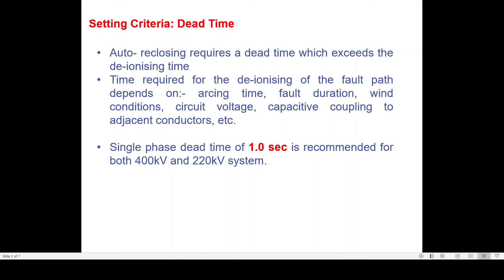Generally, dead time depends upon the arcing time of the circuit breaker, the speed of the circuit breaker — that means how quickly the moving contact separates from the fixed contact — the fault duration, wind condition, circuit voltage, as well as the capacitive coupling between adjacent conductors. For 220 kV and above, the dead time is selected as one second, but some utilities also select dead time as 600 or 800 milliseconds. This generally depends upon the circuit breaker duty cycle, which determines the minimum dead time that can be implemented in the autoreclosing scheme.